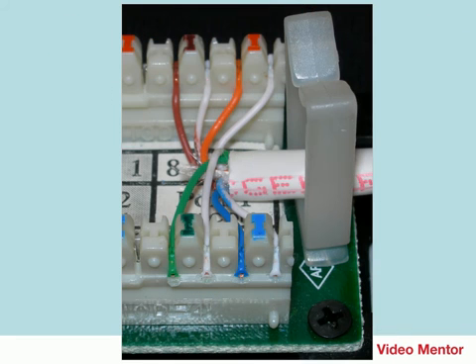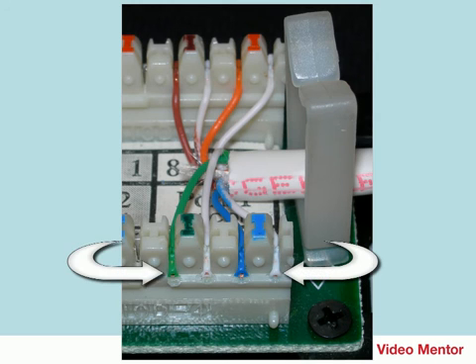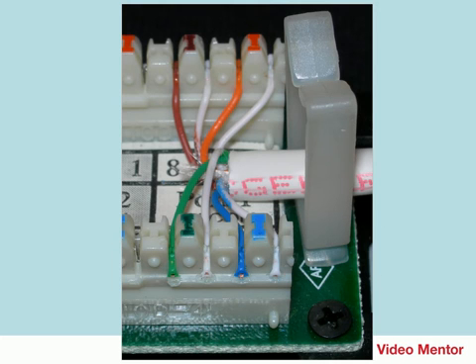Let's zoom in on the finished wiring. Here you can see that the PVC jacket is very close to the edge of the wires — there's maybe a quarter to a half inch of exposed wires. Each wire is punched all the way down to the bottom of the IDC connector, and it's trimmed off — the cut side of that tool trimmed off the end, so it's a nice clean connection.